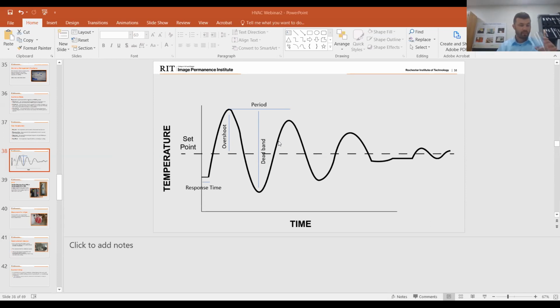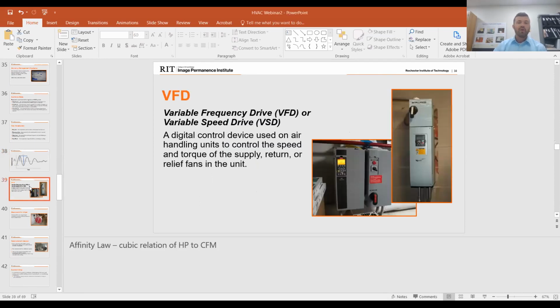There's another question about the HVAC system blowing in the spaces and disturbing the collection. Can fan air be reduced? The answer is yes. Like everything, you can reduce your fan if your fan was designed to be reduced, and you have to have a VFD on it, as we discussed earlier. If you have a VFD, the fan can obviously be reduced, and you can save significant energy. The concern about the artifacts blowing, you can back the fan speed down.